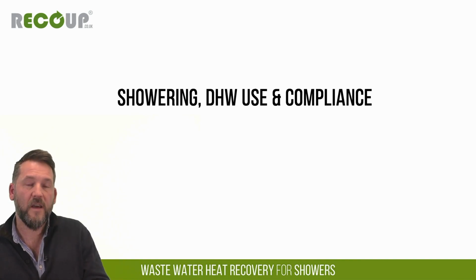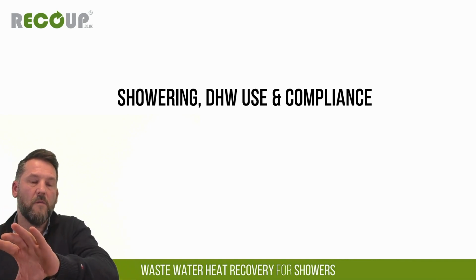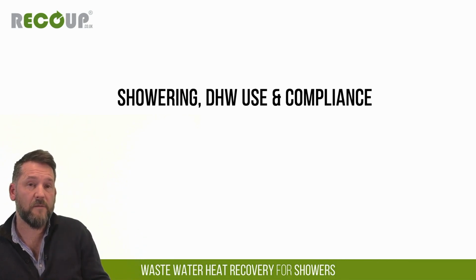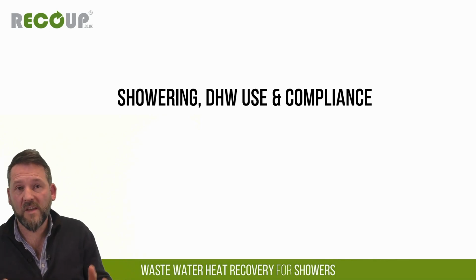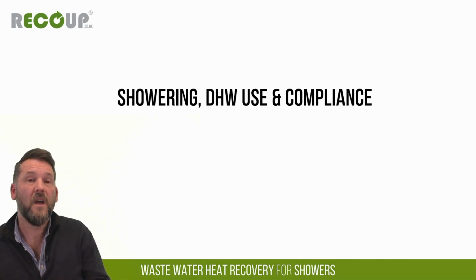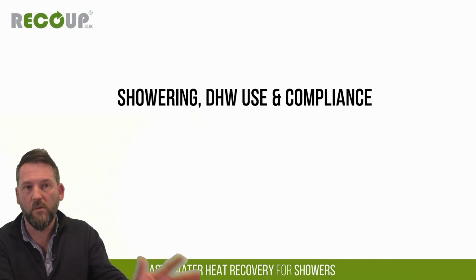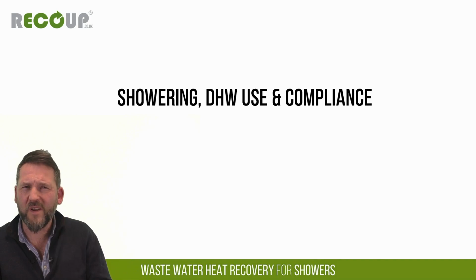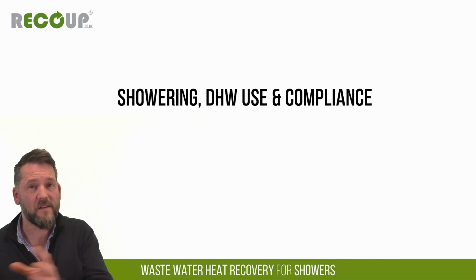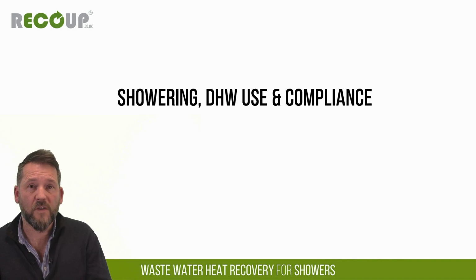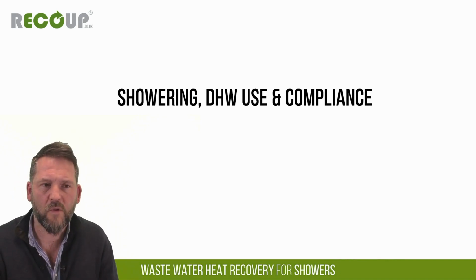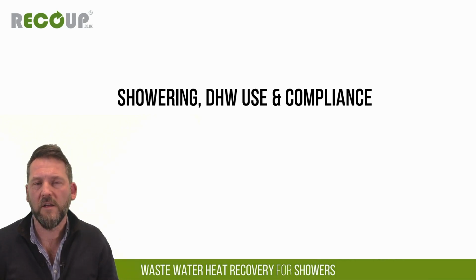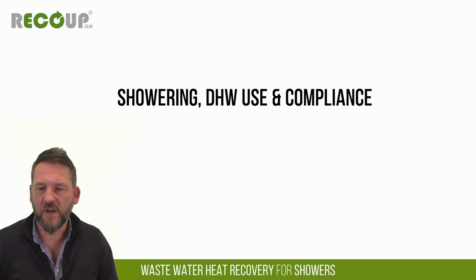In practice, even if you're installing a wastewater heat recovery unit on the ground floor with stacked showers on first and second floor, installing under system B, most of the time that 4.75 meters will cover it. So for almost all design eventualities, 4.75 meters covers it, but if you are designing in, we can always advise on that. We do have full Legionella compliance guidance separately, which we could send to anyone looking at that. From a domestic point of view, Legionella generally isn't looked at too heavily because there isn't realistically the same guidelines in place as for non-residential. But if you have further questions, we can look at that separately. In fact, we've got a knowledge-based article that deep dives into Legionella, which I can send across. Anything else, JB? Does that answer okay?